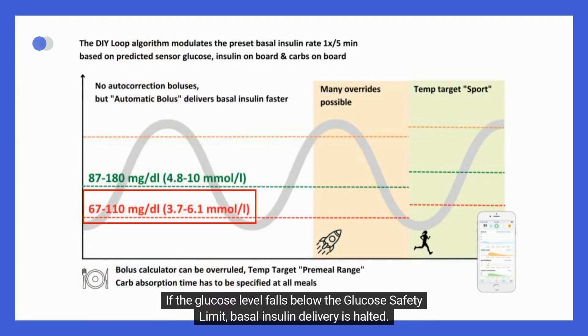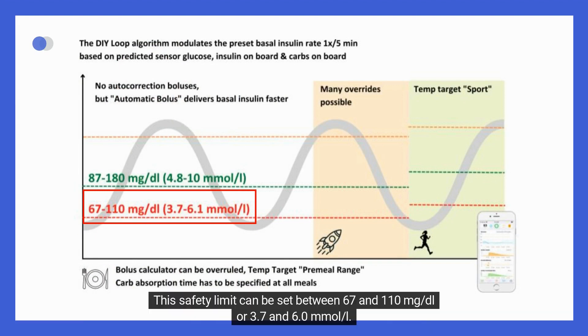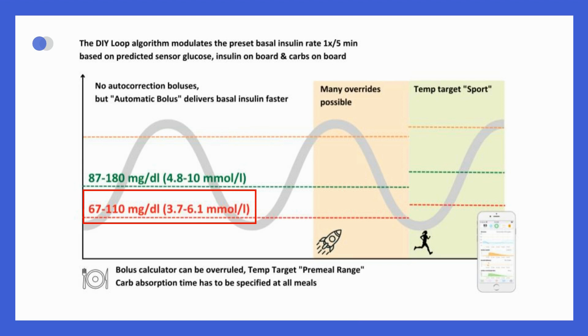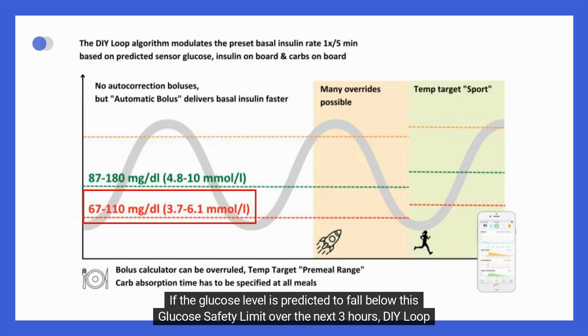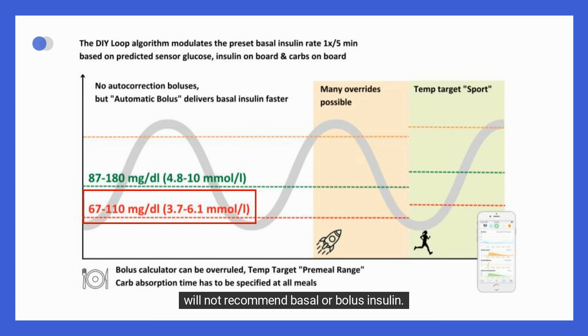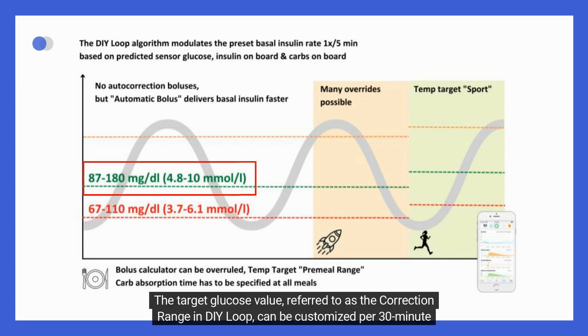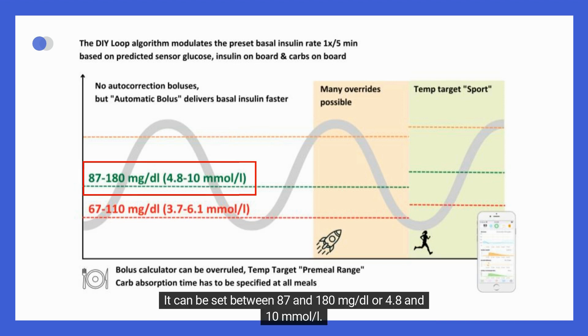If the glucose level falls below the glucose safety limit, basal insulin delivery is halted. This safety limit can be set between 67 and 110 mg/dL or 3.7 and 6.0 mmol/L. If the glucose level is predicted to fall below this limit over the next 3 hours, DIY Loop will not recommend basal or bolus insulin. The target glucose value, referred to as the correction range, can be customized per 30-minute time block, set between 87 and 180 mg/dL or 4.8 and 10 mmol/L.